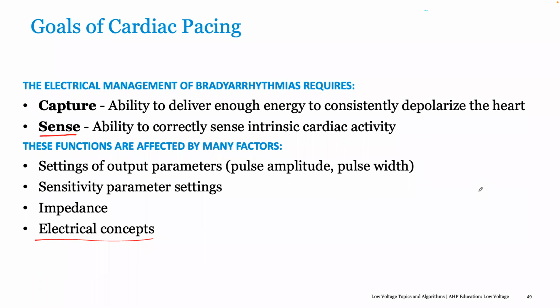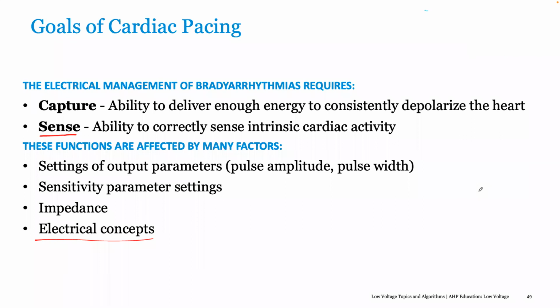I think Medtronic is a little bit higher than that. Whereas if you were putting it on manually, you can certainly put it to about 7.5 output. So with Boston, there are limitations of that. We have been caught out before in the past when somebody's threshold is creeping up, which is sensible to put adaptive or capture management on, because it does auto threshold checks and adjusts accordingly. But there are limits. So for instance, if the threshold ends up being really high, about 5 or 6, then you could run into trouble if the patient has got complete heart block or something.